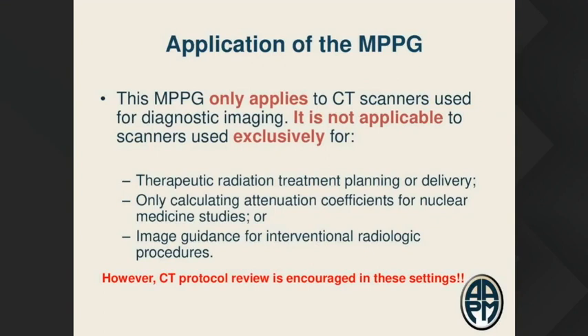This practice guideline is really intended for CT scanners used in diagnostic imaging. It's not particularly applicable for CT scanners outside of the routine diagnostic environment, including CT SIMs, CTs used for radiation treatment planning. It's also really not intended for use on hybrid systems used only for the attenuation coefficient part of the imaging chain, or where images aren't intended to have diagnostic quality. Image guidance for IR procedures was also previously considered not applicable.